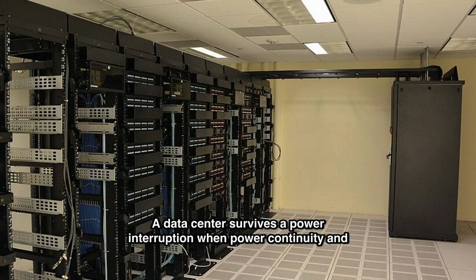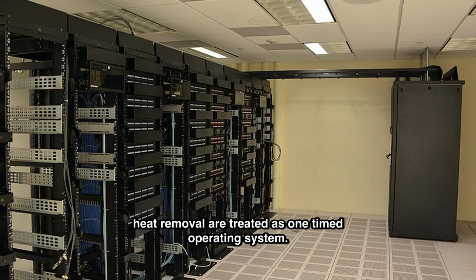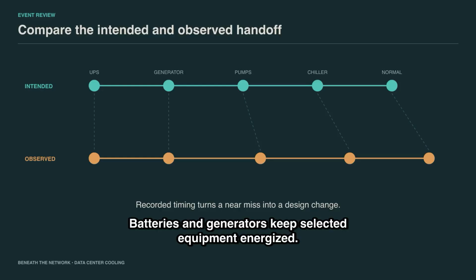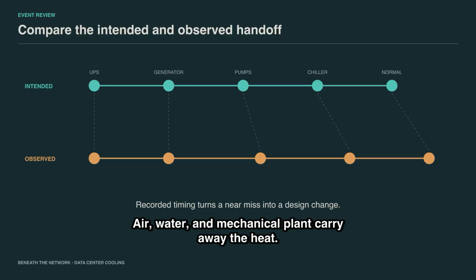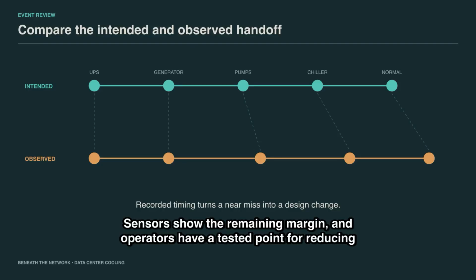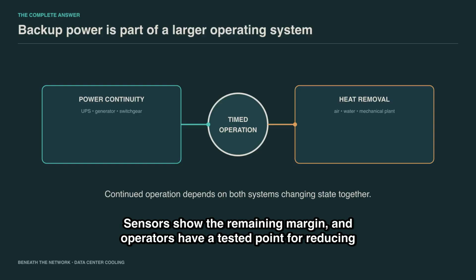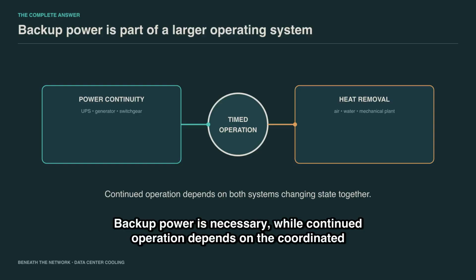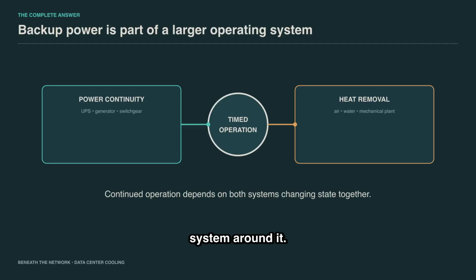A data center survives a power interruption when power continuity and heat removal are treated as one timed operating system. Batteries and generators keep selected equipment energized. Air, water, and mechanical plant carry away the heat. Sensors show the remaining margin, and operators have a tested point for reducing load. Backup power is necessary, while continued operation depends on the coordinated system around it.